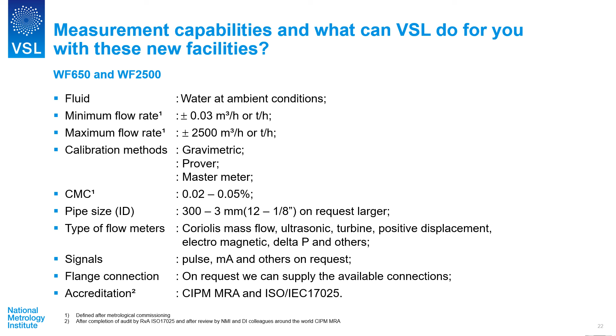Once the construction and commissioning is done for all the facilities, the European Centre for Flow Measurement can do a lot of calibrations for you. First, the liquid volume laboratory, where we can test measures and all kinds of volume instruments from small to big. We have the liquid flow meter calibration facilities, the WF650 and the WF2500 system. And we can do LNG calibrations, liquid nitrogen calibrations, and also test sampling systems for LNG.